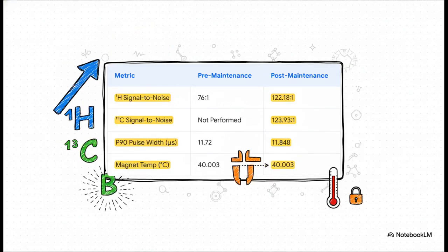This table gives us the whole story. We see that huge jump in the proton, or 1H signal, and check this out: the machine is now sensitive enough to get a great SNR for carbon-13, which they didn't even measure before. And notice that P90 pulse width? It's a tiny adjustment, just over a tenth of a microsecond. That's that final, precise bit of fine-tuning.